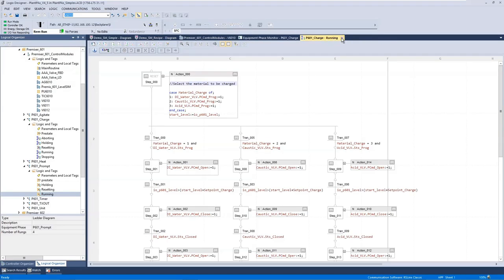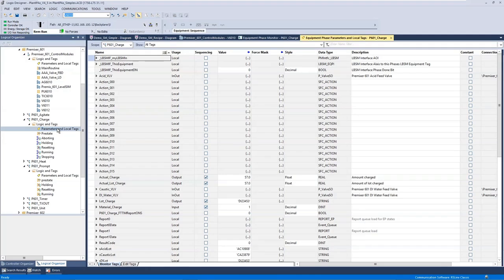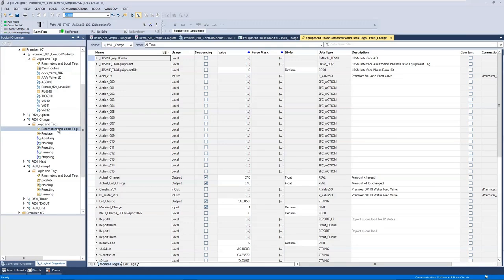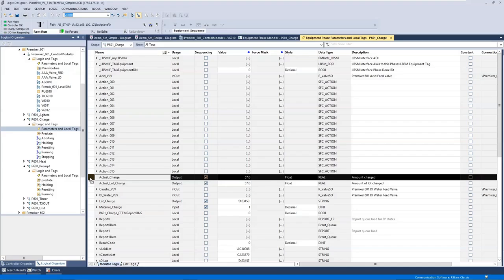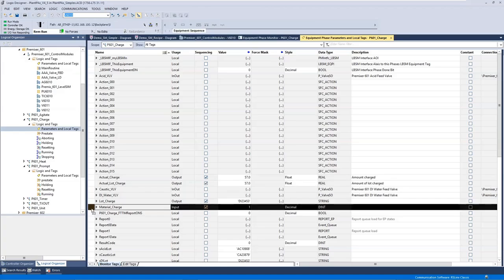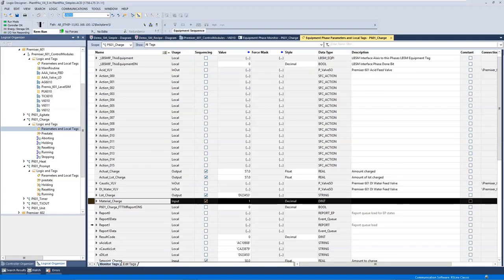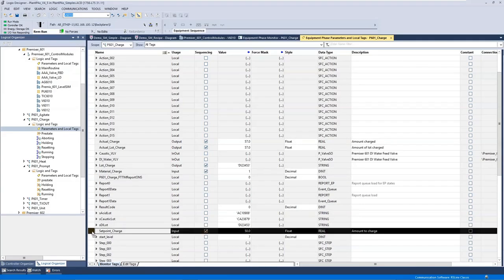Equipment phases, just like any other program, have parameters and local tags. We also have a special type of tag, where you basically identify to the Phase Manager which of these tags are inputs into my phase, things that need to be specified when I start, and which things are outputs, things I'm going to report as I'm running and when I complete. So here I look at my charge equipment phase, and I can see that I have some output values: the amount I actually charged, the lot I actually charged, and I have some input values: the material I'd like to charge before I start, the specification of that, and the amount to charge, and a bit further down, the set point.